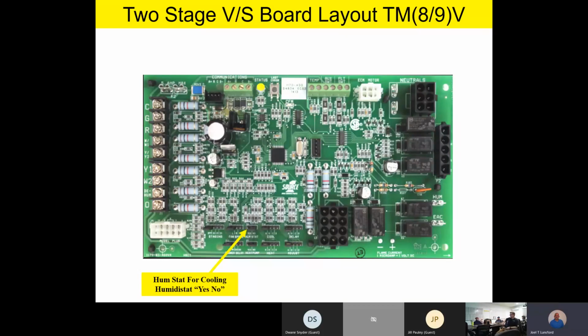There's that humidistat for cooling. Remember we talked about the dehume terminal over there. If you want to utilize that dehume terminal, you're going to put that jumper in the yes position, and then make sure you have a humidistat hooked up between R and dehume on the low voltage terminal. If you're not going to use that dehumidification for cooling function, make sure that is in the no position. It comes from the factory no, but make sure it's in the no position if you're not going to use that dehume function on the low voltage terminal strip, because if you have it in the yes position and you don't have anything hooked up to the dehume terminal, it will never allow the fan to go above 80% airflow. Remember, we talked about that: less airflow, colder evaporator, more dehumidification during our cooling cycle. But if you have that in the yes position, make sure you've got a humidistat hooked up between dehume and R. Otherwise, you'll never get your fan above 80%.